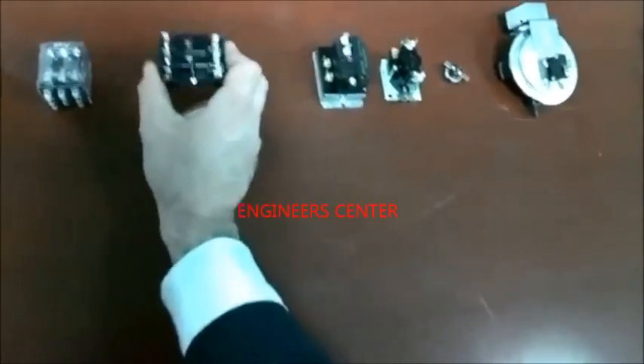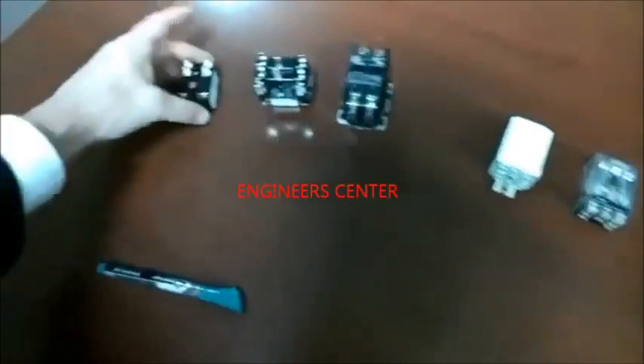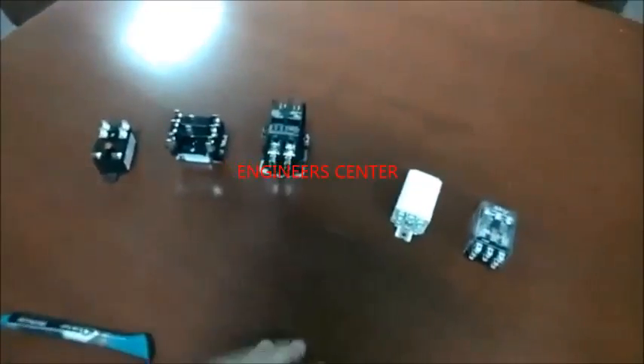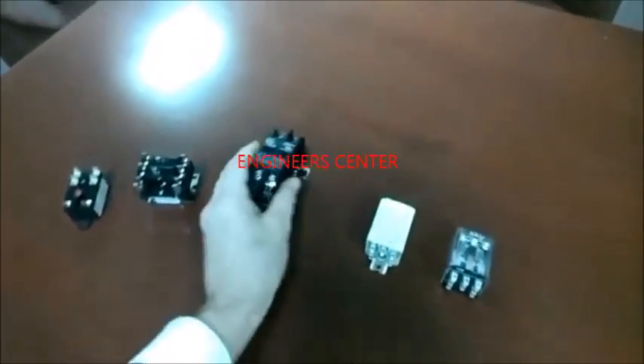So here we have another relay. It just handles more duty, and that's the difference between these 3. Light duty, medium duty, heavy duty contactor. So the more amps you're going to be pulling, the heavier duty relay you're going to use. And so it's a contactor, it's a relay, but they do the same thing.